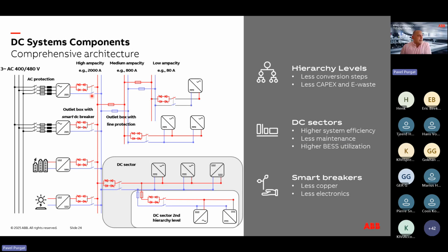Now, what you can see here is that the protection is provided not only through electromechanical switches or not only through fuses, but also through semiconductor devices. And you might be wondering why is that necessary, and I will explain that later. However, one other thing is we don't need them everywhere. So we need to design the systems and divide it into sectors and decide what type of protection is appropriate for the sectors. Now, this outlook is based on one of the industrial alliances, and there can be some other, but what they have usually in common is that the system is split into zones or sectors, and that is utilizing smart breakers or solid-state circuit breakers to connect these systems.